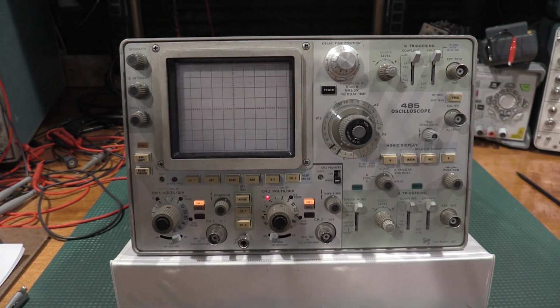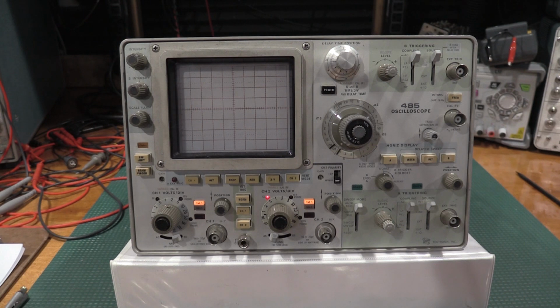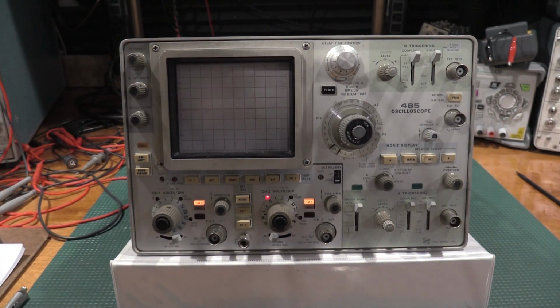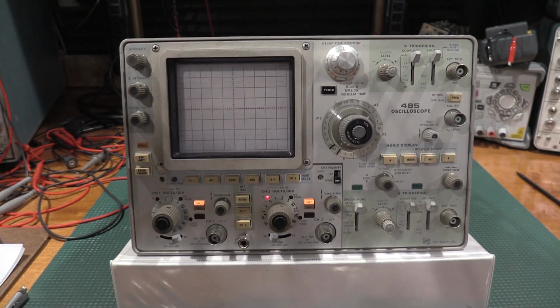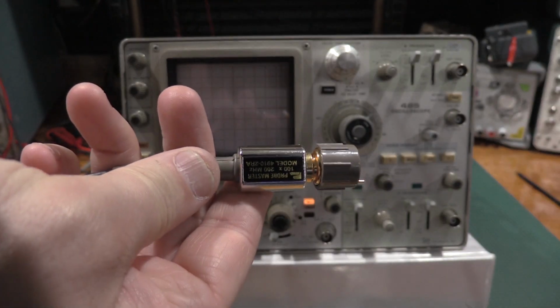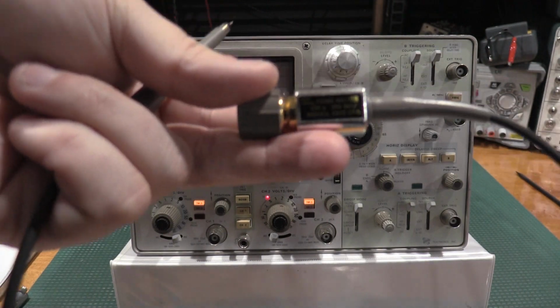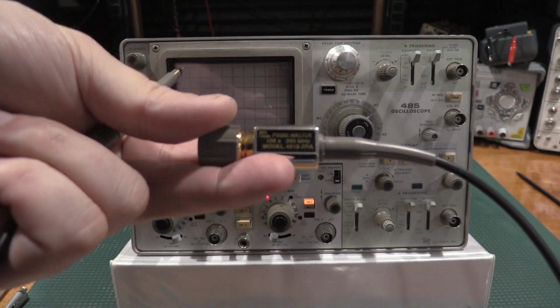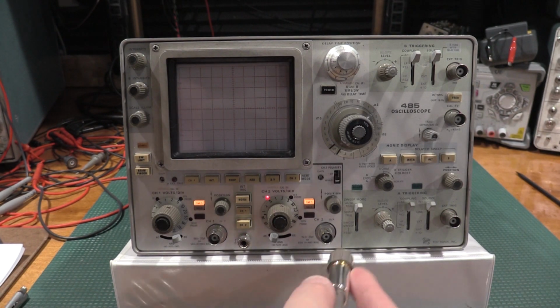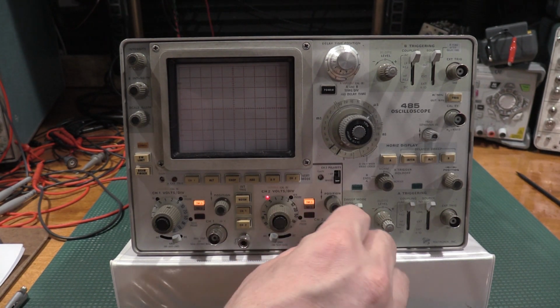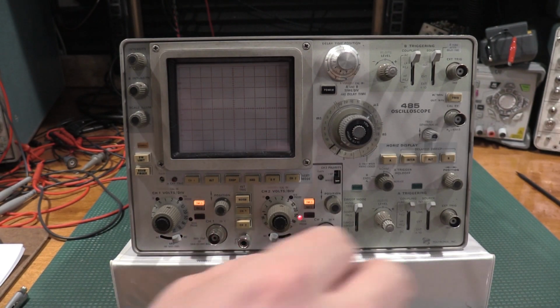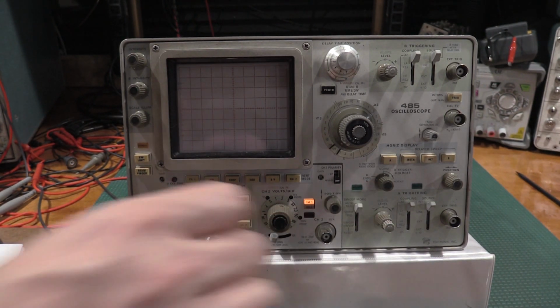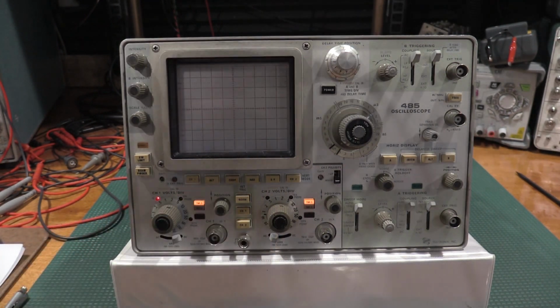So I'm also going to test. I have an indicating probe at 100x. As soon as I locate it, I only have one, but I do have a Probe Master probe, so I should be able to check the 100x setting as well. Okay, here is my 100x probe from Probe Masters, and that's upside down, of course. 50-50 shot, 90% of the time I get it wrong. And if we plug this in, we should see we're on 100 and 100. So all my indicator LEDs are working.